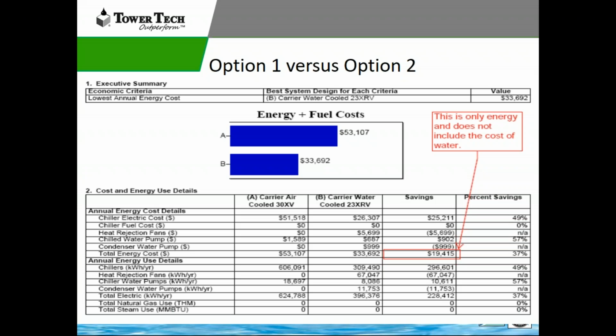So when we do the operational analysis and look at the energy cost of operating option one versus option two, this is oftentimes where we stop the analysis, and from an end user standpoint, they're like, man, that Carrier 23XRV / Tower Tech system has an operating cost of $33,000 a year on an 800-ton chiller plant versus an air-cooled system at $53,000 per year. It's a savings of $19,000. I mean, that is significant. There's no way water costs that much.